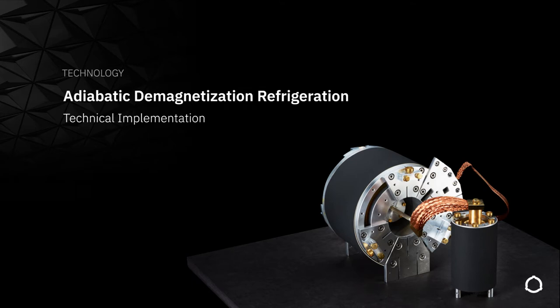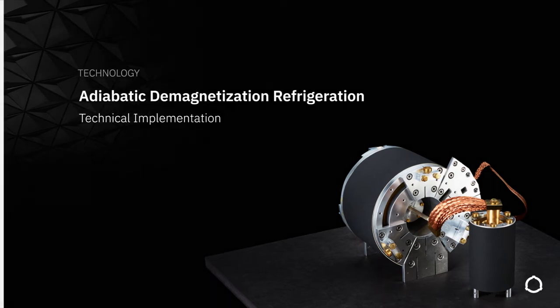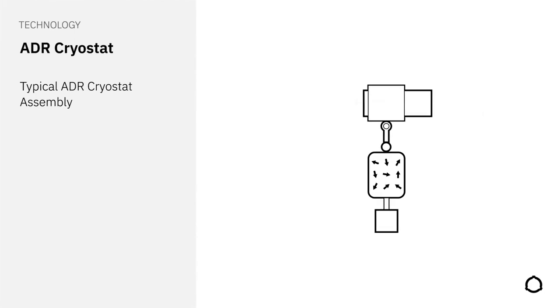Now, let's have a look at how ADR is technically implemented to build a sub-Kelvin refrigerator. In a cryogen-free setup, we use a closed-cycle cryocooler to provide a main thermal bath of about 4 Kelvin. It will be used to pre-cool our ADR cooling medium to a temperature where the total entropy of the material is dominated by the magnetic entropy. The cooling medium is connected to the cryocooler through a heat switch on one end and to the sample stage that contains the experimental setup on the other end. Finally, the medium is surrounded by a superconducting magnet.